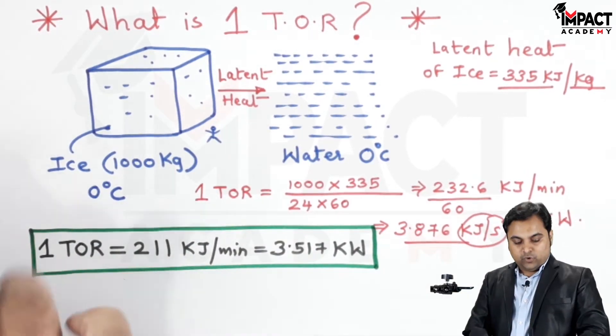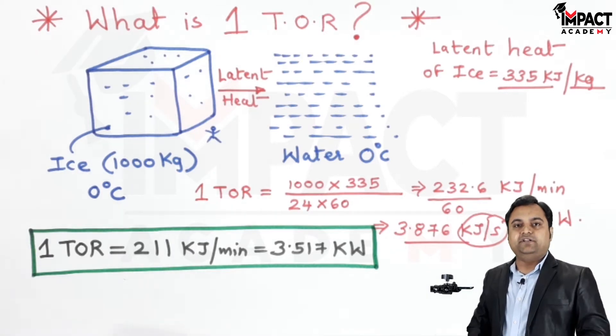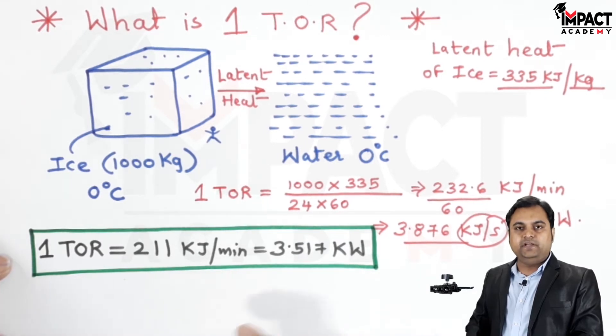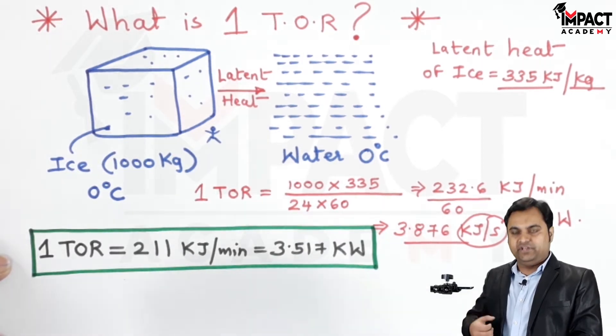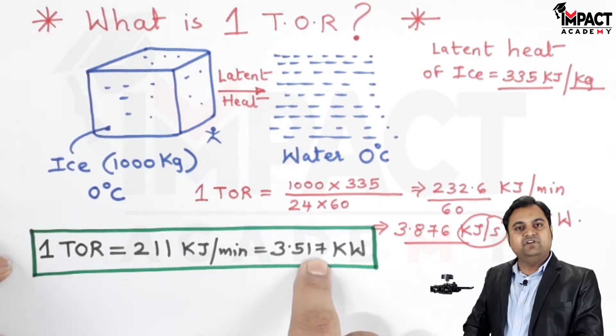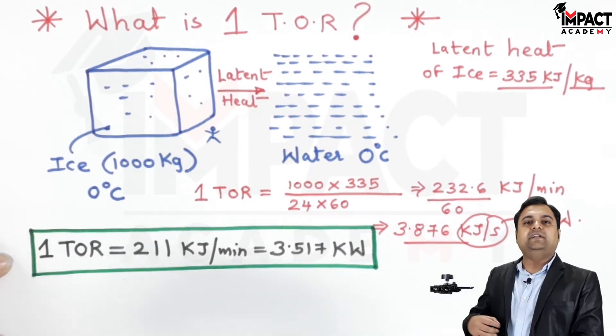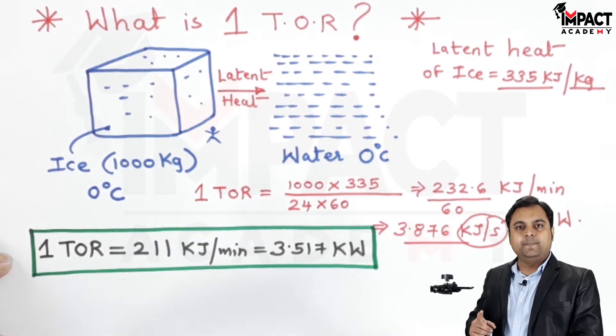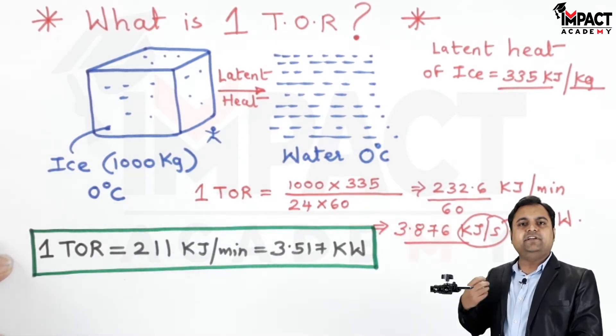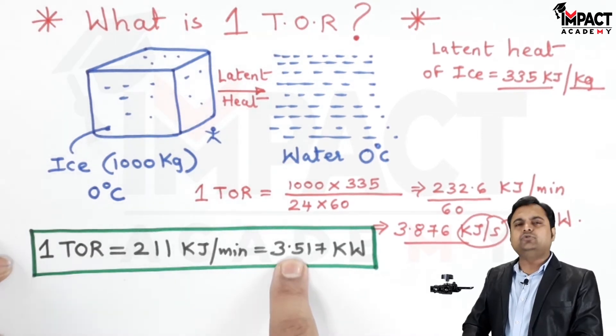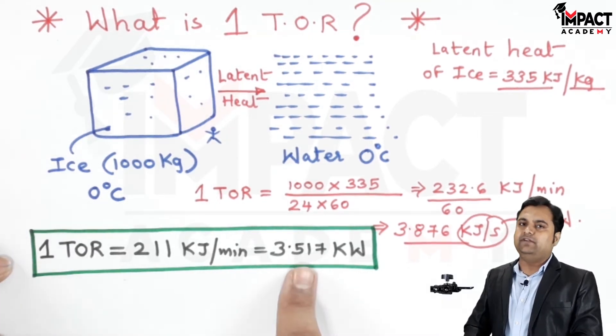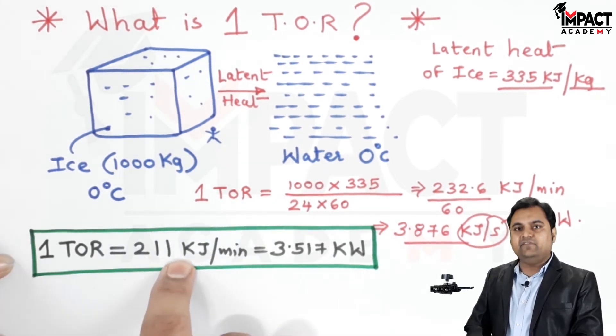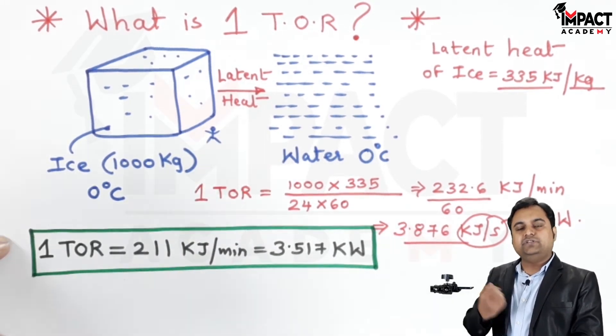Whenever we talk about one ton of refrigeration, it means such a system would be continuously absorbing heat of 3.517 kilojoules per second from the required space. If we are having an AC of one ton, that one ton AC would be removing heat from the room equivalent to 3.517 kilojoules in one second, or in a minute that AC would be removing 211 kilojoules from the room.